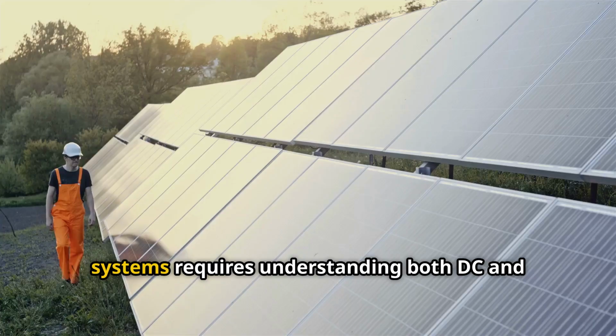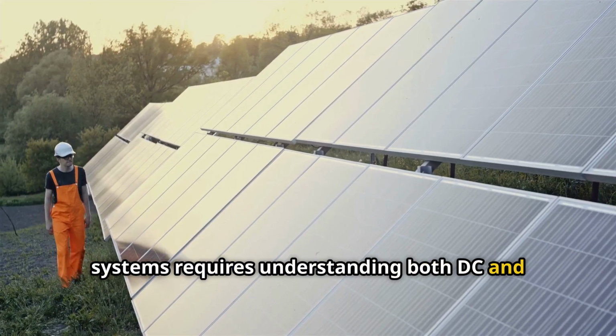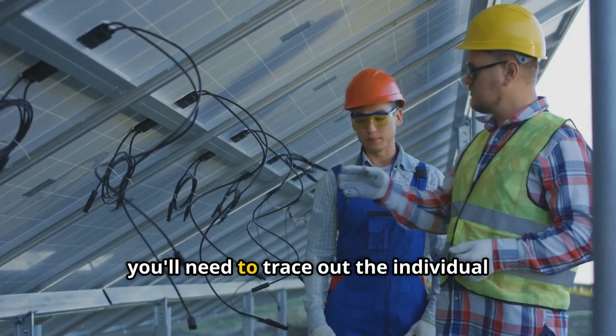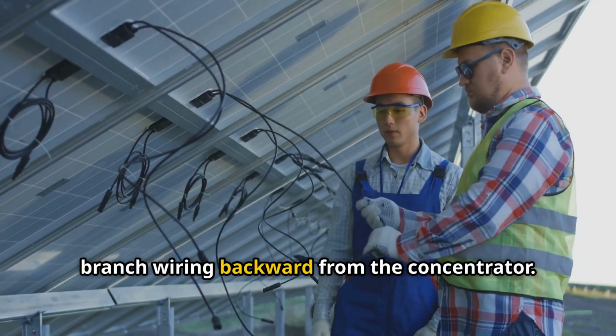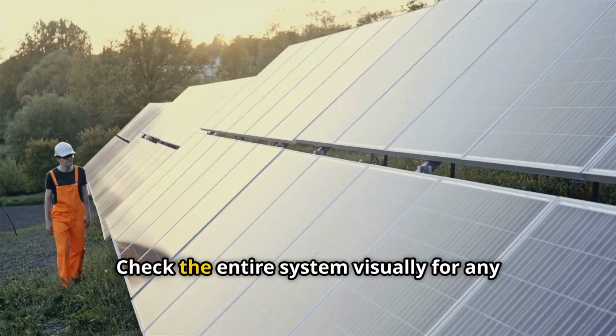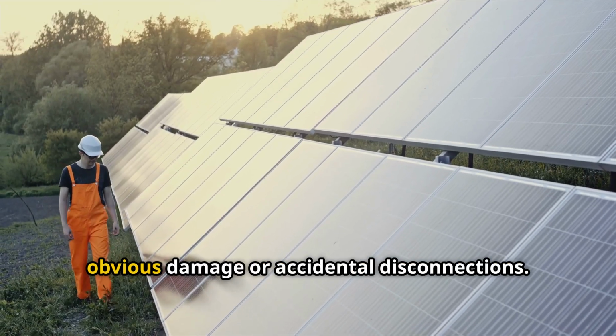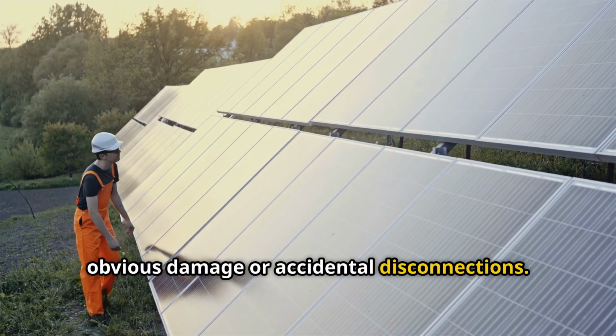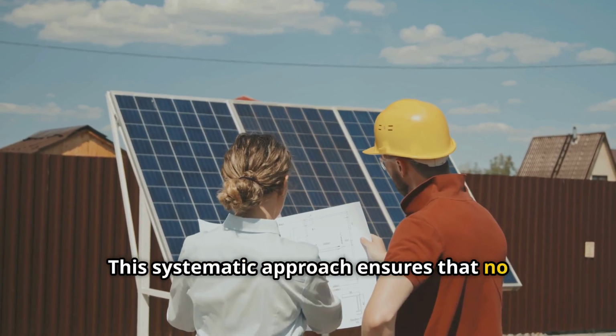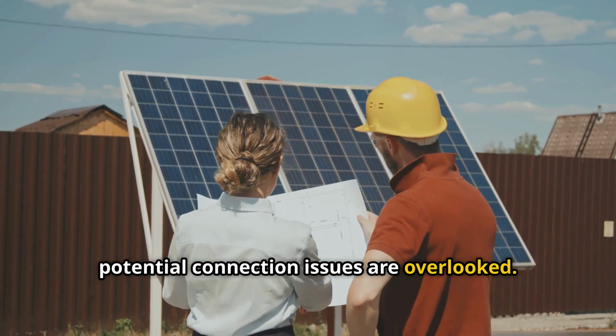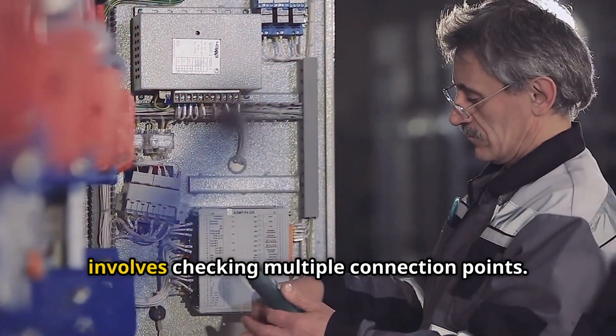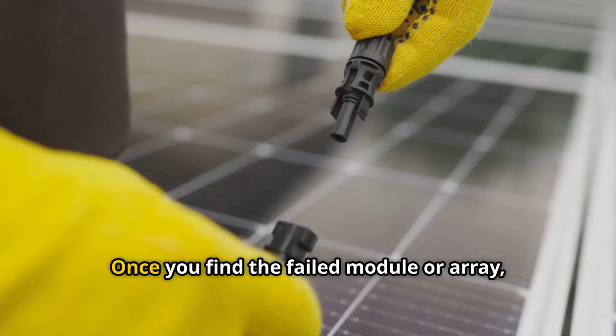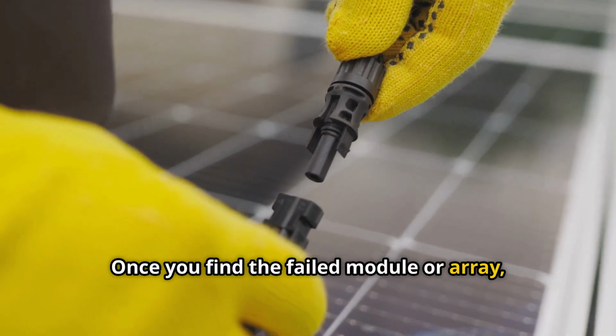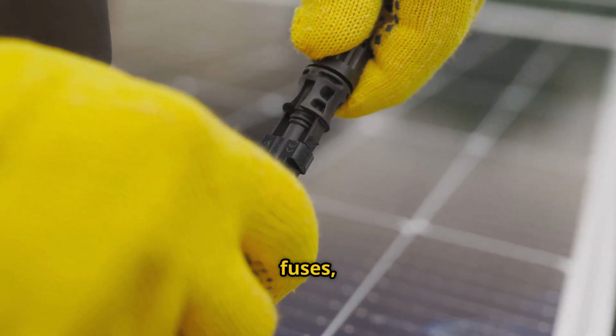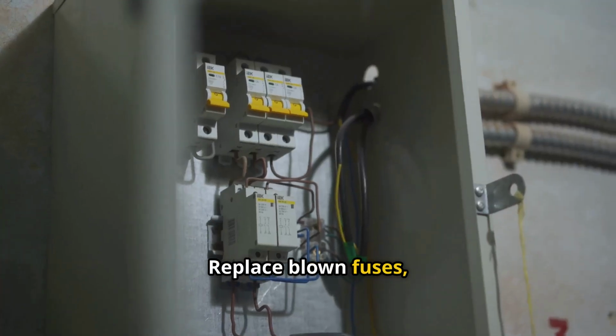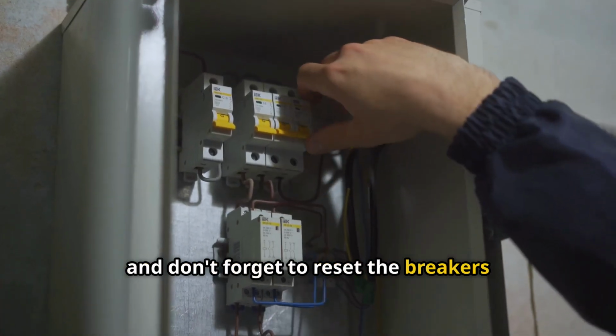Electrical troubleshooting in solar systems requires understanding both DC and AC side issues. So, you'll need to trace out the individual branch wiring backward from the combiner box. Check the entire system visually for any obvious damage or accidental disconnections. This systematic approach ensures that no potential connection issues are overlooked. Professional electrical troubleshooting involves checking multiple connection points. Once you find the failed module or array, check all wires, switches, fuses, and circuit breakers. Replace blown fuses, and don't forget to reset the breakers and switches.